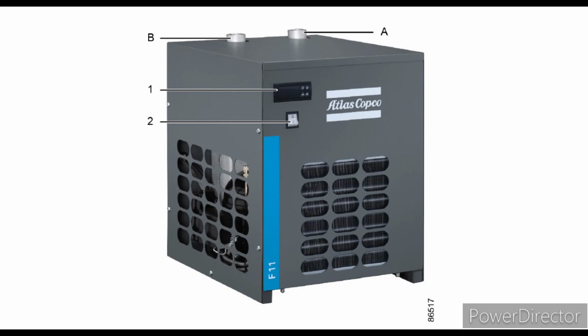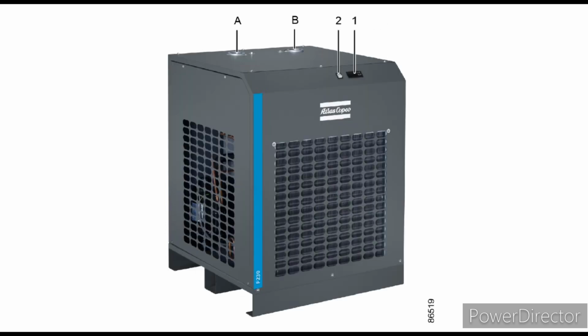Basically, compressed air contains naturally occurring moisture, which can negatively affect applications that require moisture-free air. Dryers are the common solution for removing moisture content. One of the most popular options is the refrigerated air dryer because of its ability to reach an acceptable dew point in general industrial plant air applications. This dryer can reach a dew point of 3 degrees, plus or minus 5 degrees.